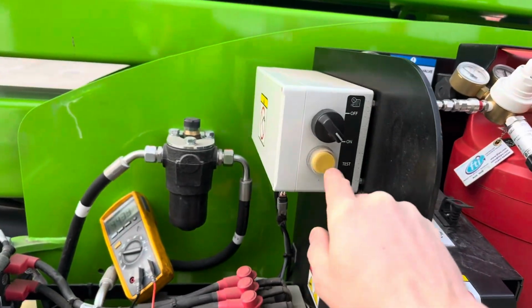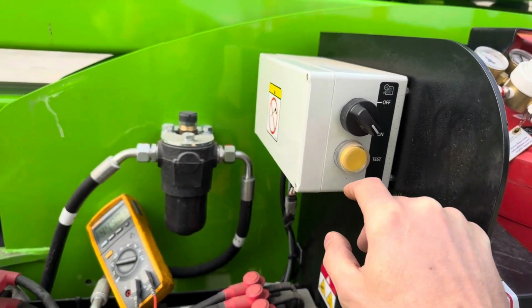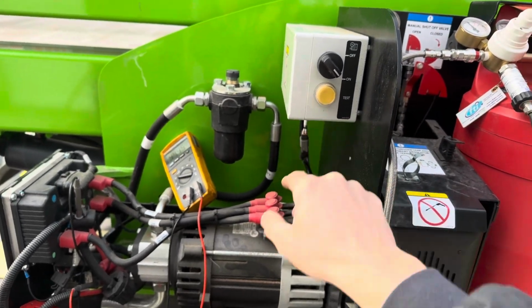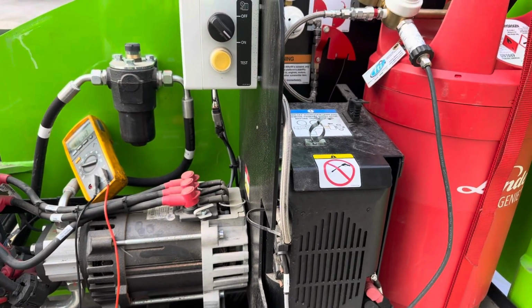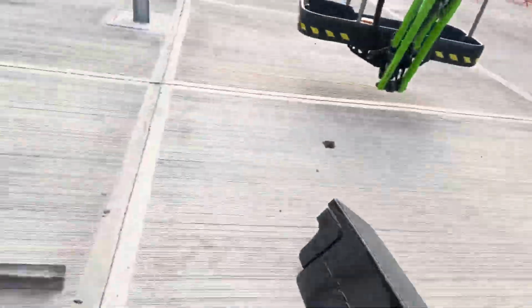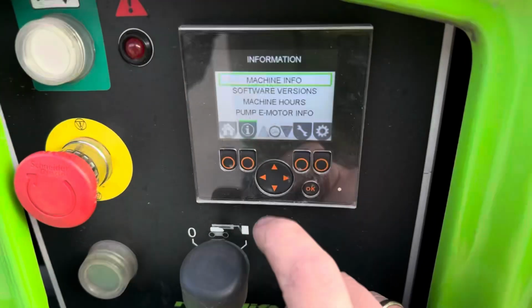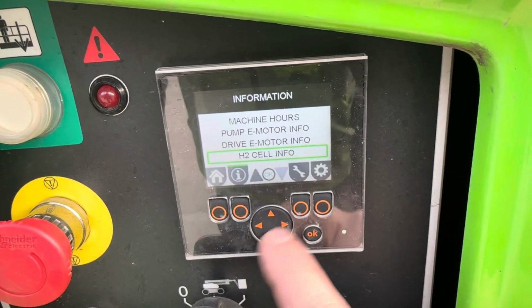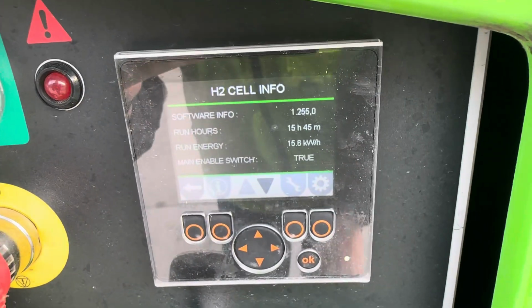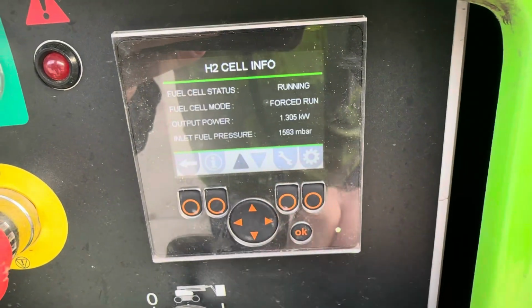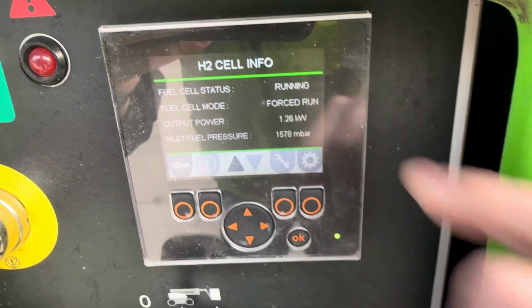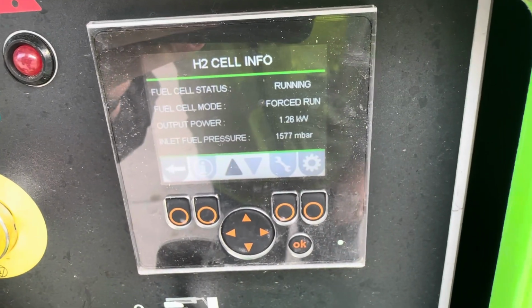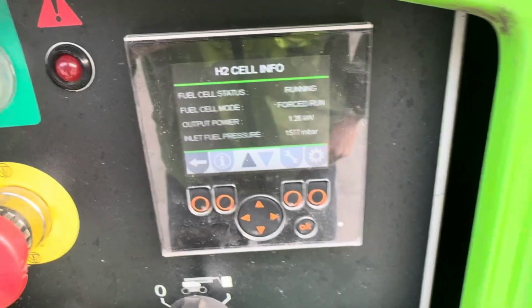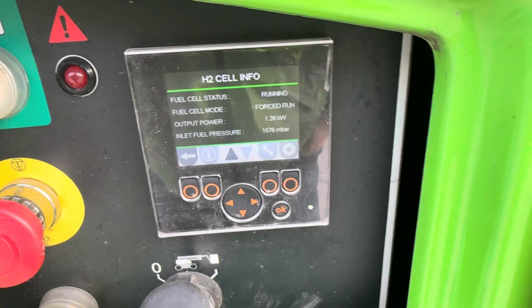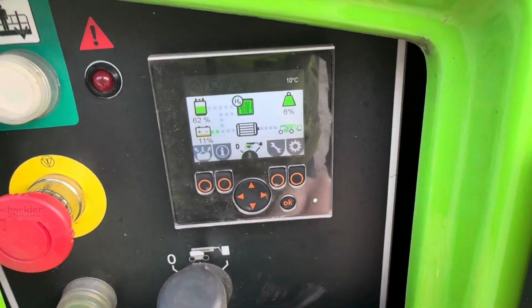So what I've done now, I pressed and held that button for about 15 seconds, and that started a force charge, which you can check on the display. If you go to info and then H2 cell info, you see the cell is enabled, the fuel cell is running, and the fuel cell mode is forced run. I forced a run because we need to recover this machine to move out of here to get it charged. Okay, that should help me out.